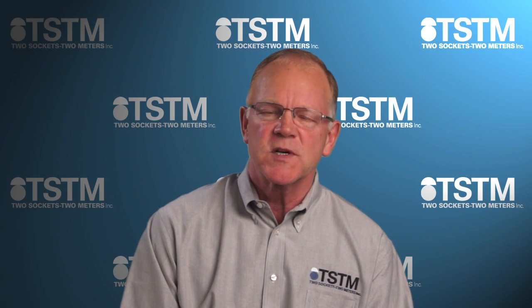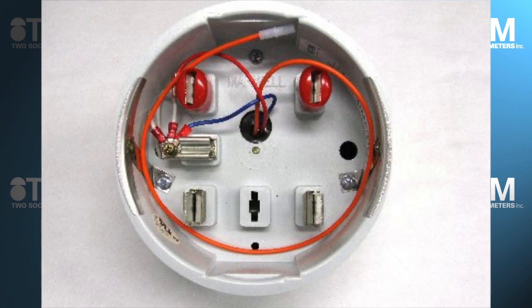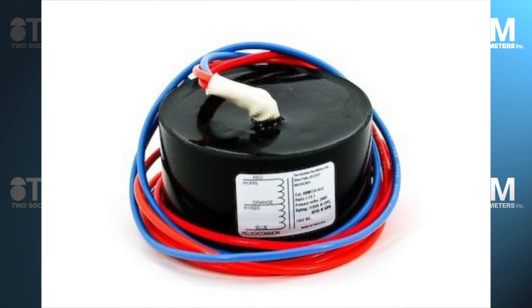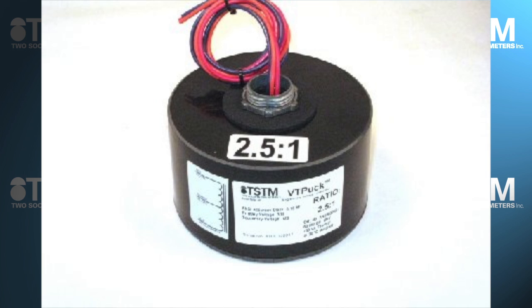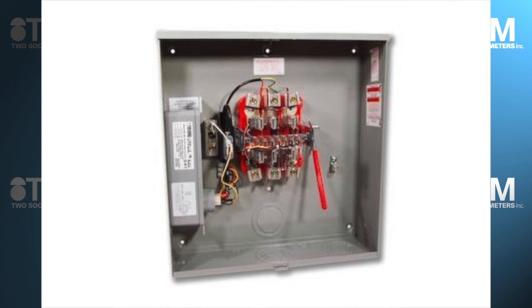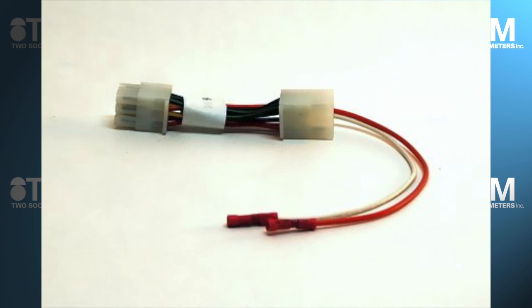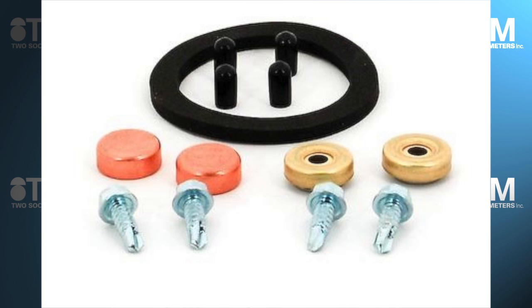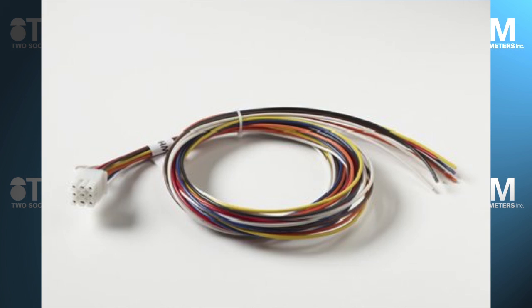A list of some of the accessories that go along with the VT pack: meter adapters, hockey pucks (auxiliary power transformers), VT pucks (metering accuracy hockey pucks, just a bit larger). We have custom meter sockets made to your configuration with custom test switches and custom color coding. We have wiring harnesses made to any length and color coding, including stripes. We have external mounting kits to mount the VT pack on the exterior of meter sockets. And we have a terminal strip that lets you extend the primary or secondary of the VT pack harness so you can mount the VT pack a significant distance from the meter socket.